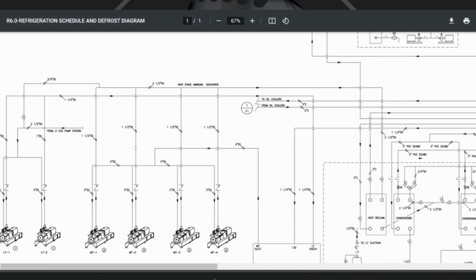And we're running a liquid pump on the liquid overfeed system that we wouldn't normally run. So that additional horsepower on the liquid pump, and the fact we have to run at a much lower suction temperature, is what's causing the inefficiency. But you're saving more money on other things. Water treatment is extremely costly, it can cost a lot of money per year. Because of the way you have it set up, you're basically saving that as well as the price of the chemical.